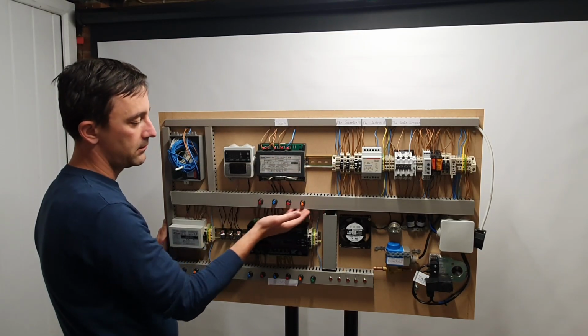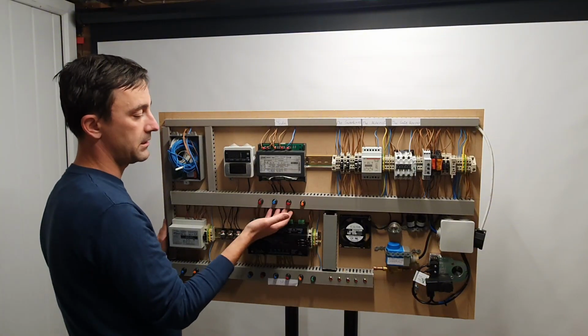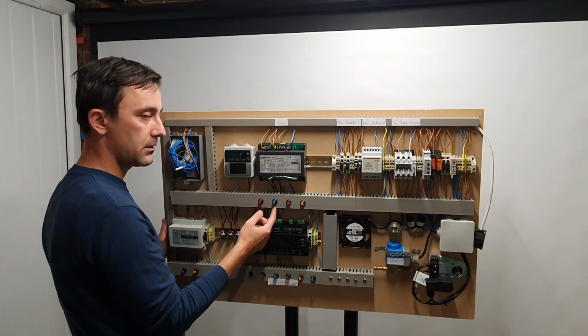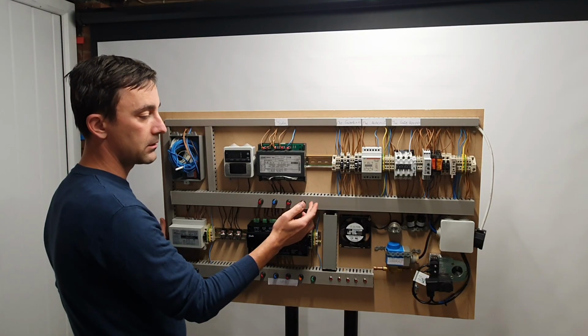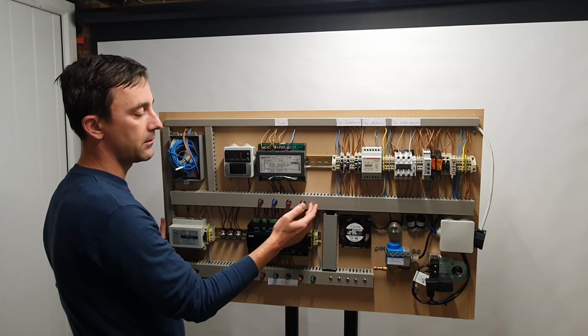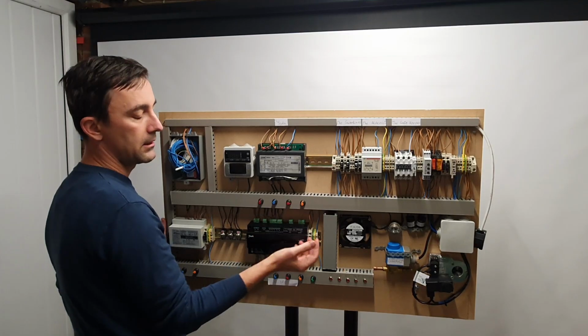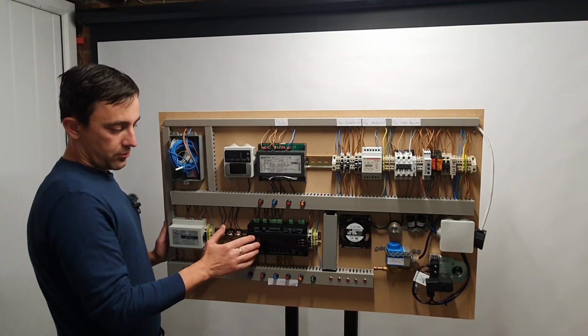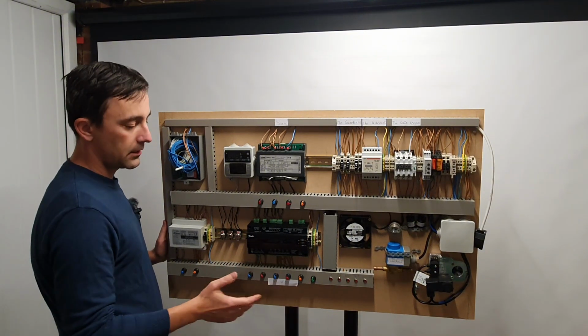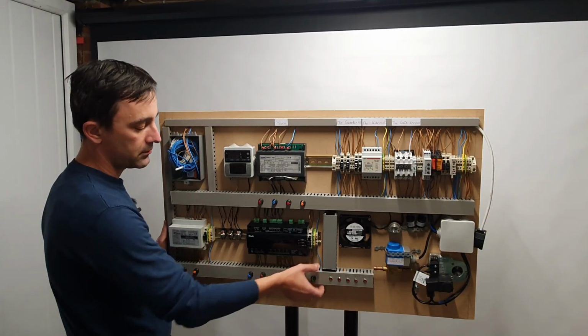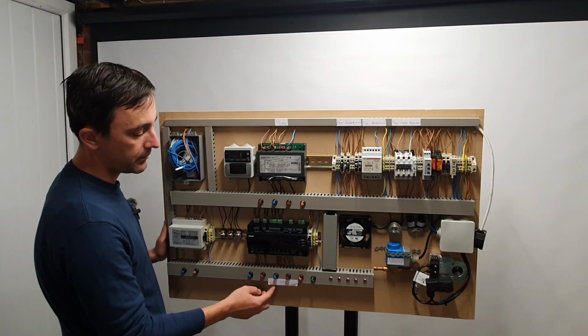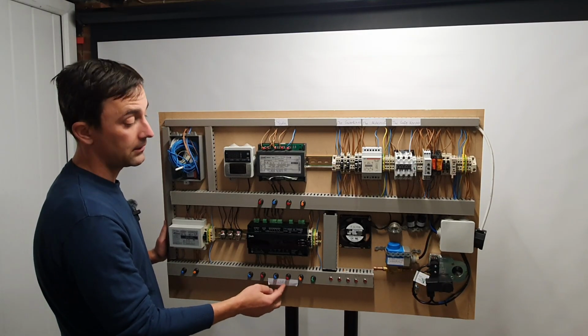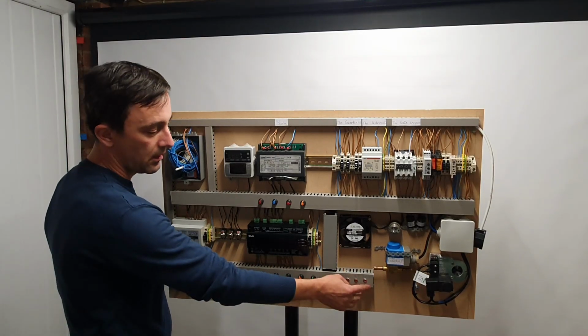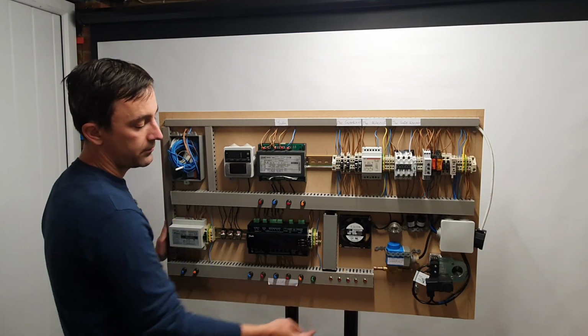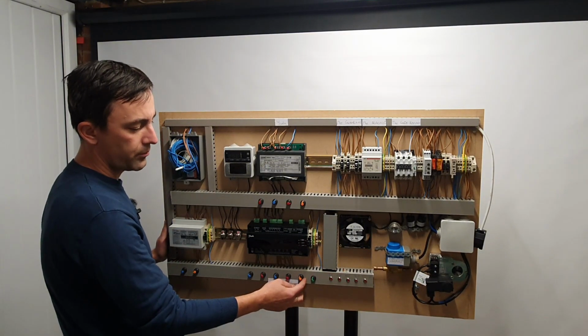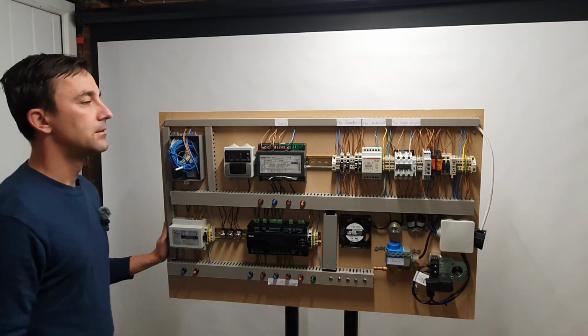This controller has 4 temperature probes or 4 potentiometers, air probe, evaporator probe. Probe 4 can be put as a product probe, or it can be configured as a condenser probe, and obviously probe number 3, that's a condenser probe as well. This Danfoss controller, being a bit more versatile, I decided to make the most of it and fit all 6 probes. So you would have air on, air off, evap in, evap out, or evaporator inlet, evaporator outlet, which are used for the electronic expansion valve, a defrost probe, and a product probe. So yeah, quite happy with it.